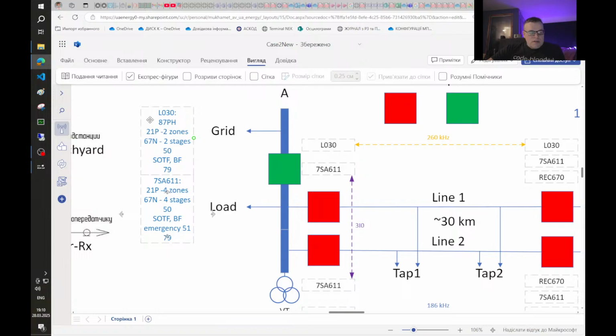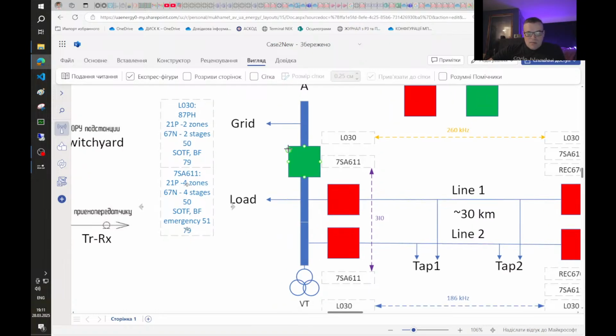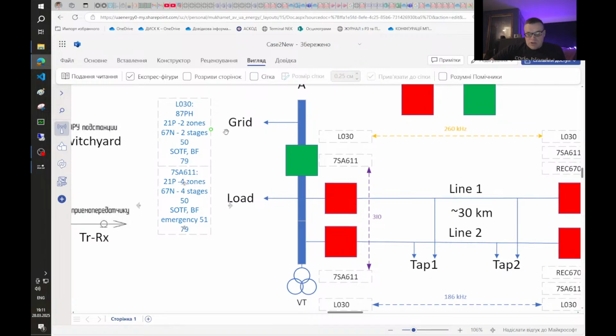So let's review some functions that are enabled in the devices. So L030 has phase differential protection, two zones of distance protection, two stages of earth fault protection, overcurrent, SOTF function, breaker failure protection, but also auto reclosing function. For SOTF functions, usually the second zone of distance protection and the second stage of earth fault protection are used.